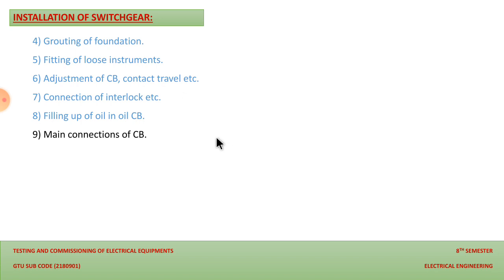The ninth point for the installation of the switchgear is main connection of the circuit breaker. When we have installed our circuit breaker, we need to connect it in our system. The main connections should be done according to the guidelines provided, and according to the notation provided on the box of the circuit breaker. The 10th point is earthing connection. We have discussed earthing, why it is necessary and why it is important. After installing the circuit breaker and connecting all necessary connections, this is the last part that we have to connect, that is earthing.